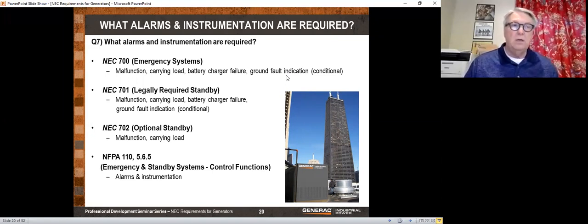If you've got a generator necessary to preserve human life, why in the world would you want it to trip because you've got a swamp cooler that has a ground fault on it? In addition, that's conditional. Basically it has to be over 1,000 amps, 480 volt, before you actually need that. So ground fault indication just indicates that there's a ground fault. It'll have a light and generally an annoying buzzer, but it does not actually trip the generator.